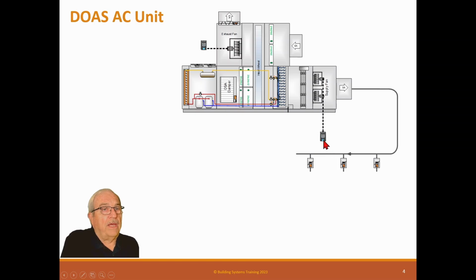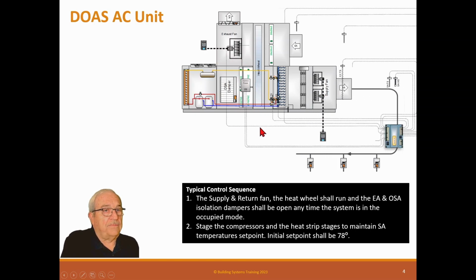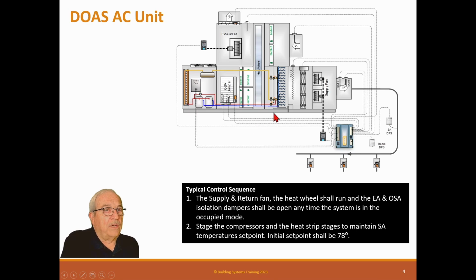So these normally have VFDs here and VFDs here on the supply fan and exhaust fan. They, of course, have a refrigerant circuit, and these normally have hot gas bypass so they can run when it's colder out there. The sequence is: supply and return fan, the heat wheel shall run, and the exhaust air and outside air isolation dampers will be open anytime the system is in the occupied mode.